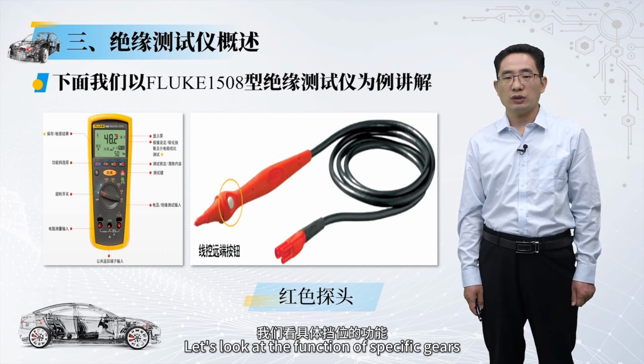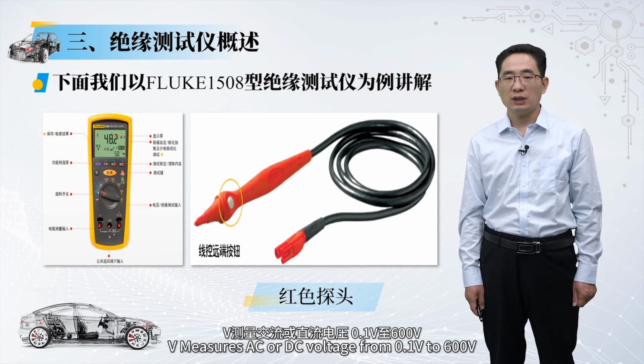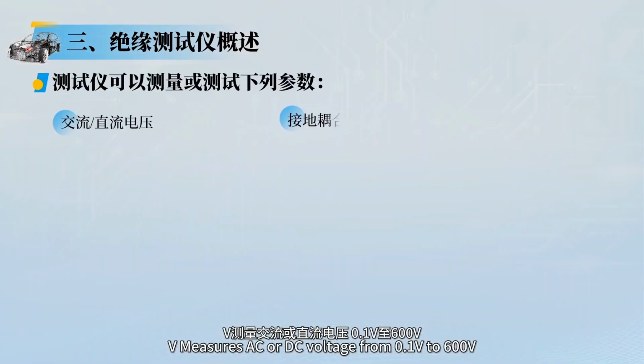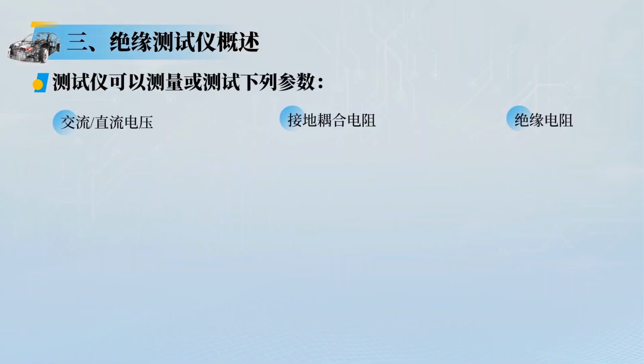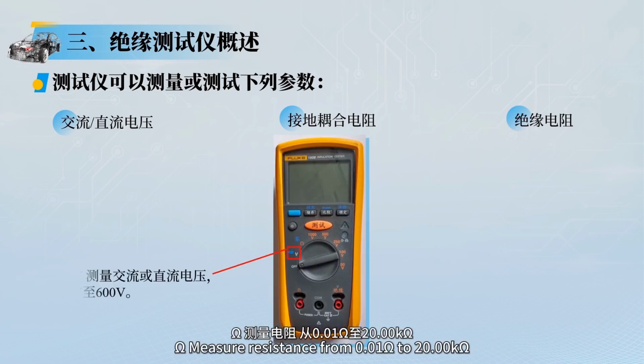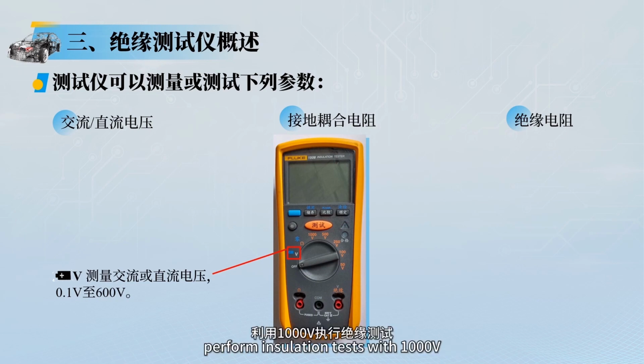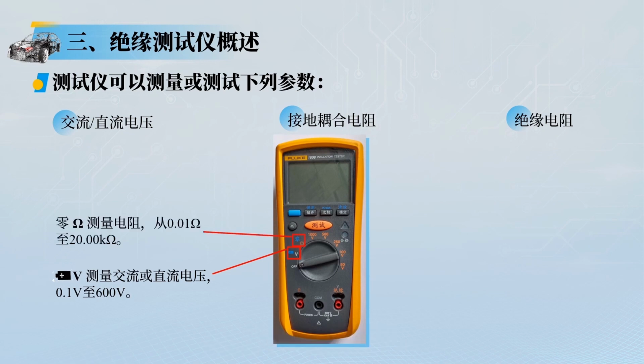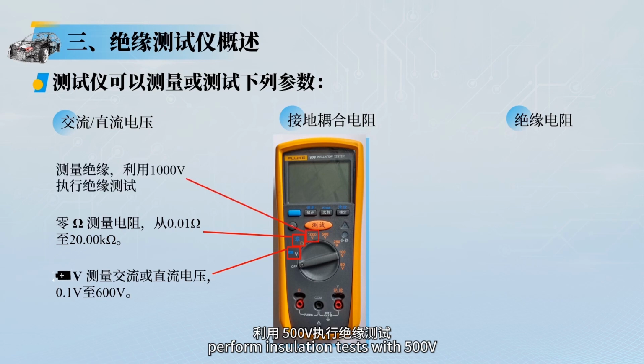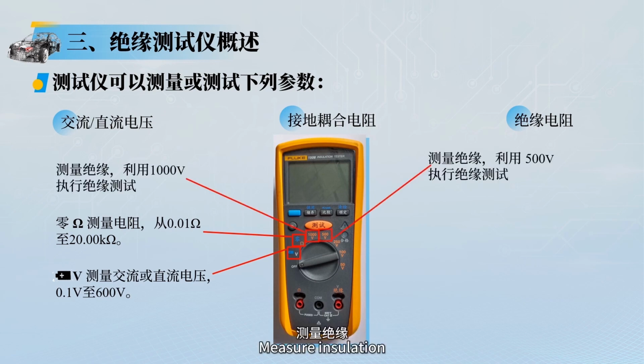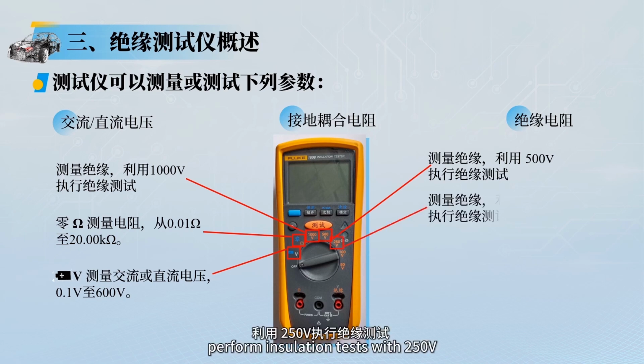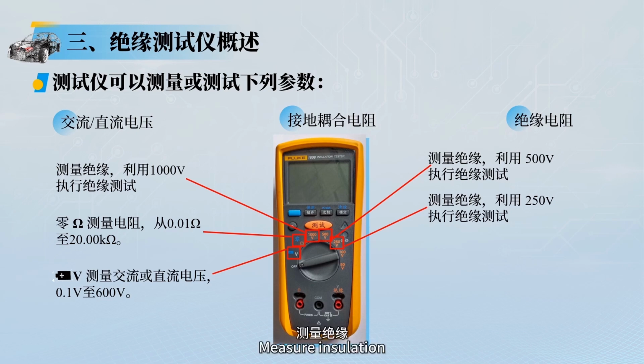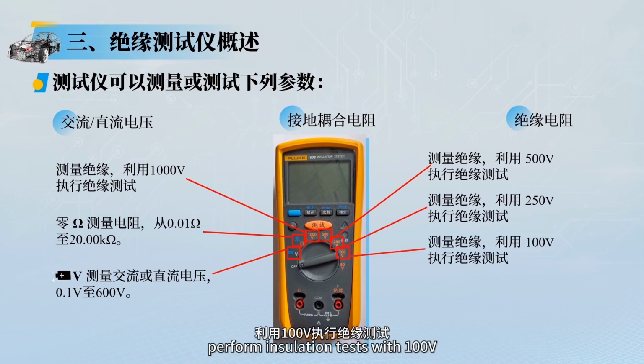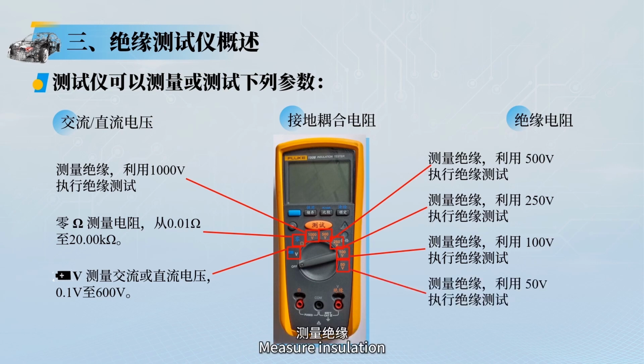Let's look at the function of specific gears. V measures AC or DC voltage from 0.1 volt to 600 volts. Zero ohms measures resistance from 0.01 ohm to 20.00 kiloohms. Measure insulation: perform insulation tests with 1000 volts. Measure insulation: perform insulation tests with 500 volts. Measure insulation: perform insulation tests with 250 volts. Measure insulation: perform insulation tests with 100 volts. Measure insulation: perform insulation tests with 50 volts.